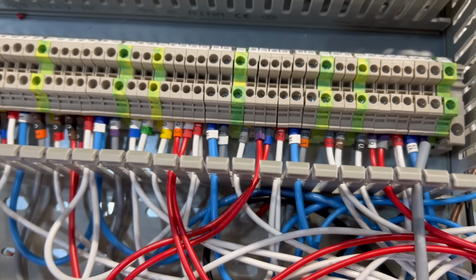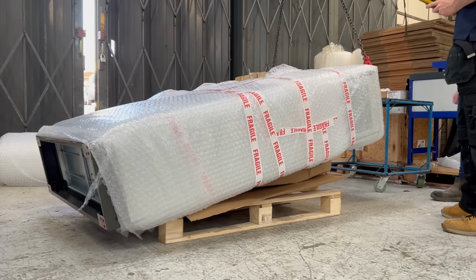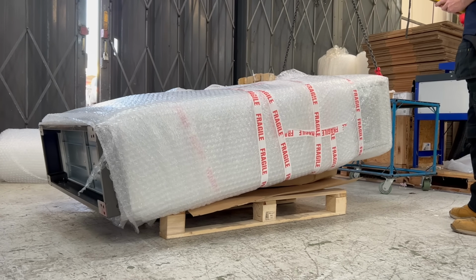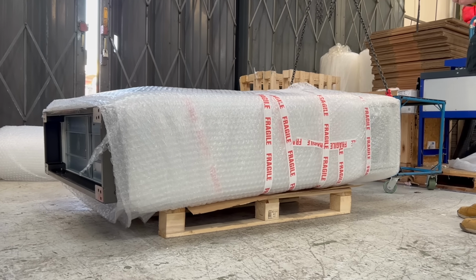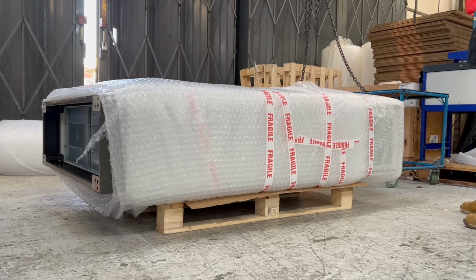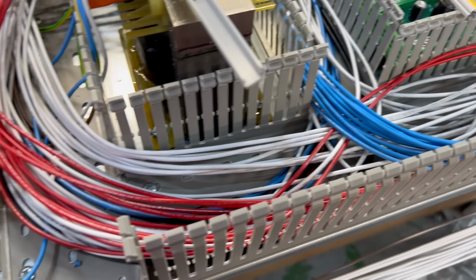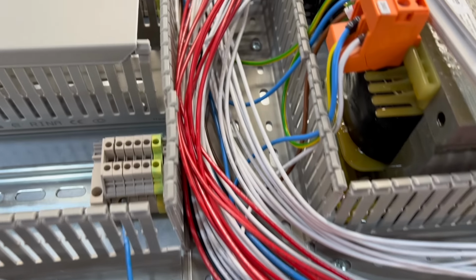the panel in the workshop, and then when they get taken away to be installed on site, the wiring in the building is brought into the panel and connected to the relevant terminal. This makes installation quicker, easier, and reduces the chances that a mistake will be made on site by trying to bring a conductor through the panel and into a component.